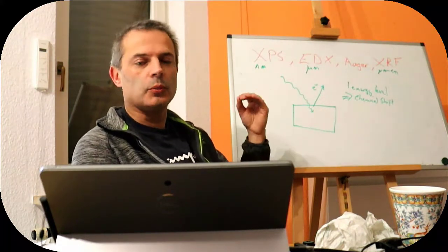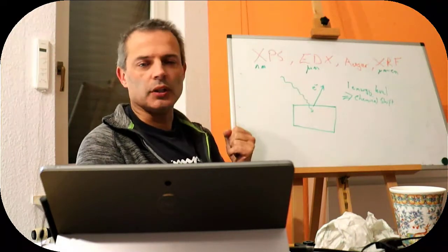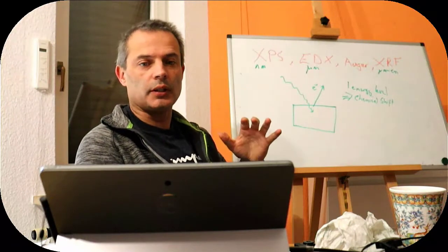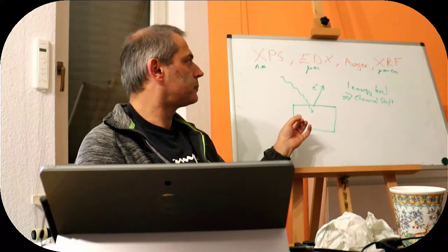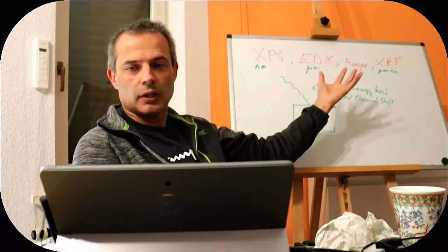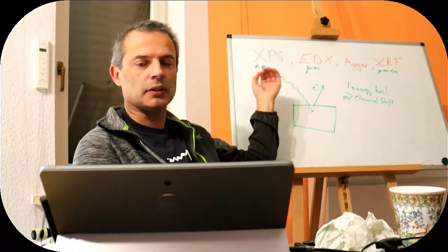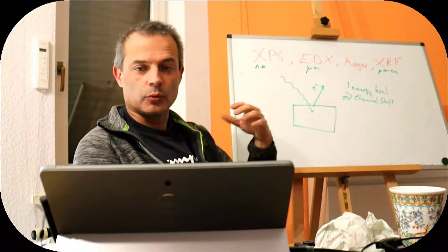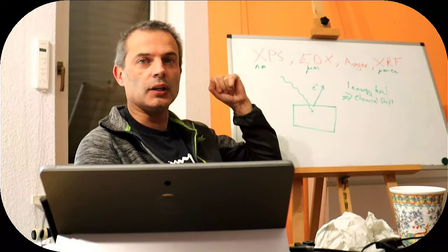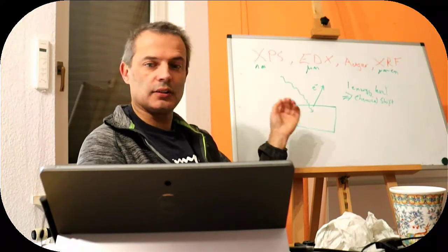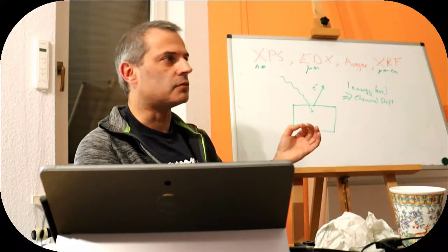This is important because obviously if we have a metal, we're only going to be looking at the metal oxide. It's going to be a lot of nanometers, but still we'll typically not get through the metal oxide unless it's something with a very, very thin oxide layer. The electron has a low energy, and so it's also affected by the charging of the surface, so we have to watch out in X-ray photoelectron spectroscopy how we treat our surface. Ideally it wouldn't charge up, but if we coat it with something, which is what you do in electron microscopy, you can't even get to the original material. It also means that if we've got any dirt on the surface, that is what we will see.